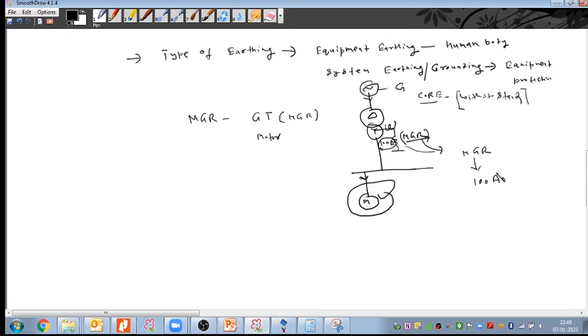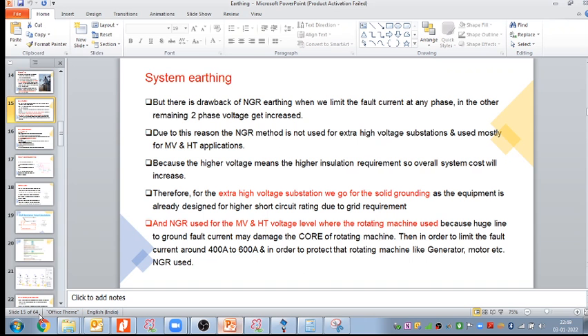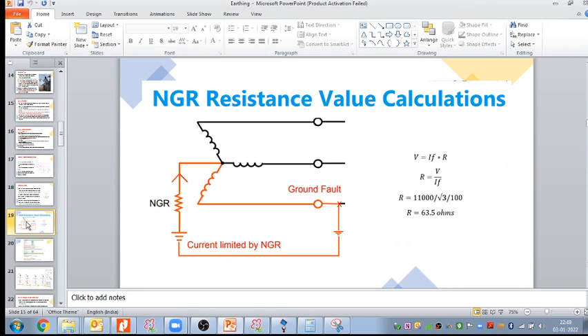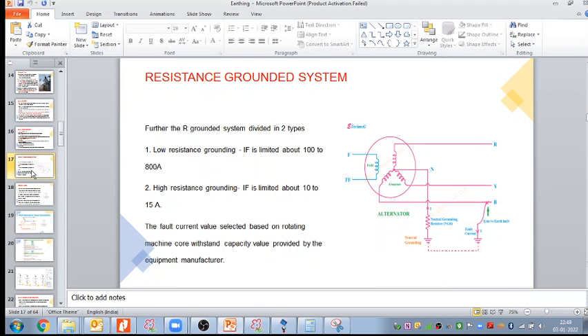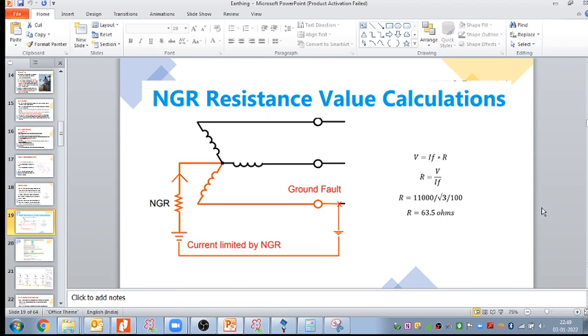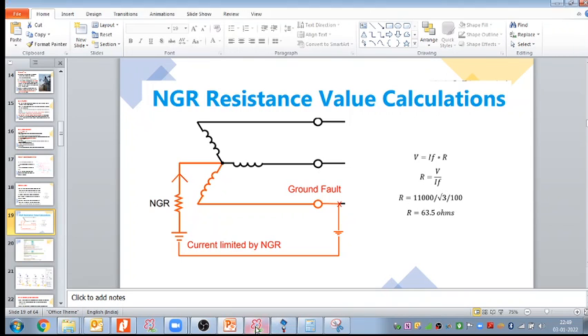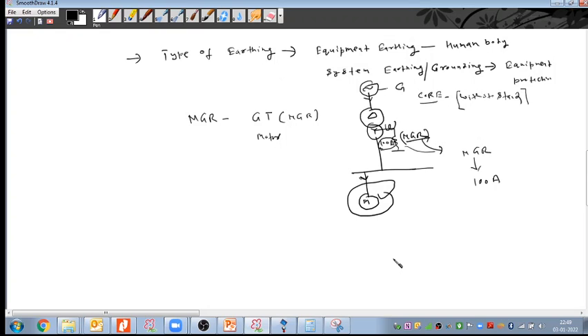How to calculate this NGR value? Here we have a formula on this page. Resistance R equals V divided by IF, where IF is how much current we want to allow. Suppose my line voltage is 11 kilovolts. We convert this 11 kilovolts into the phase voltage, so we have to divide by √3, right?